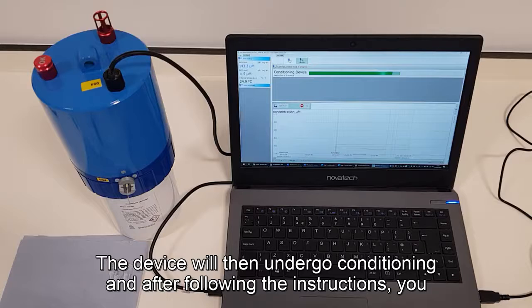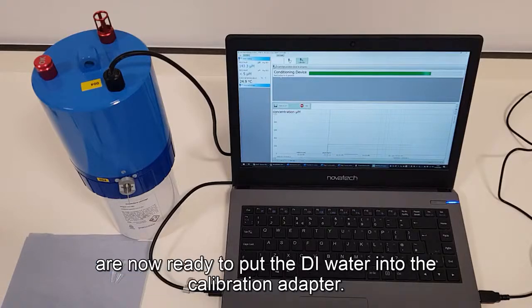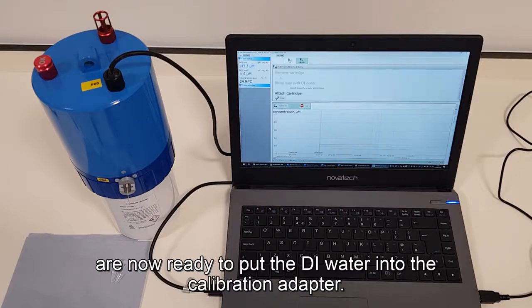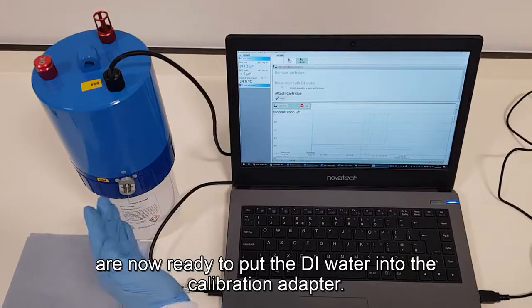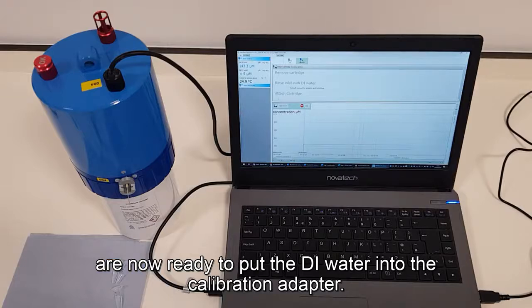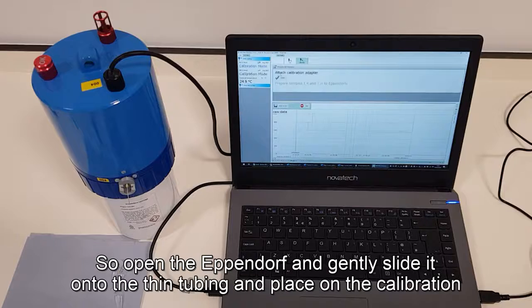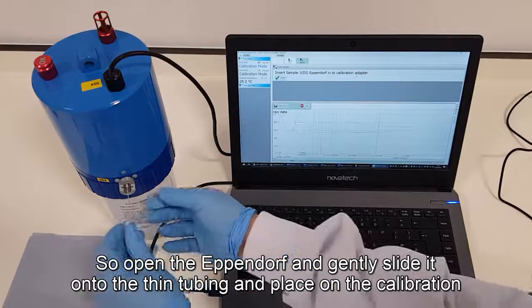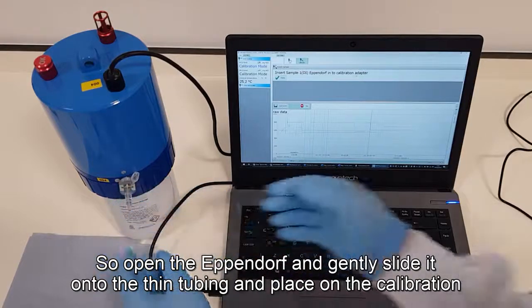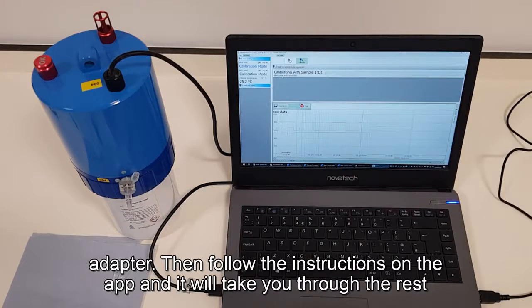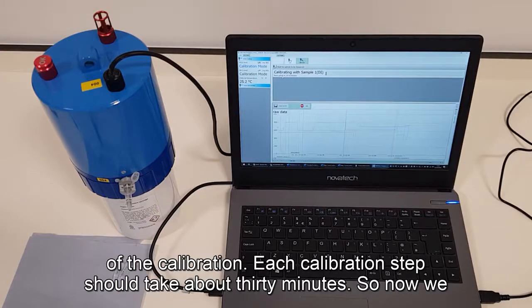The device will then undergo conditioning, and after following the instructions, you are now ready to put the DI water into the calibration adapter. So open the Eppendorf and gently slide it onto the thin tubing and place onto the calibration adapter. Then follow the instructions on the app and it will take you through the rest of the calibration. Each calibration step should take about 30 minutes.